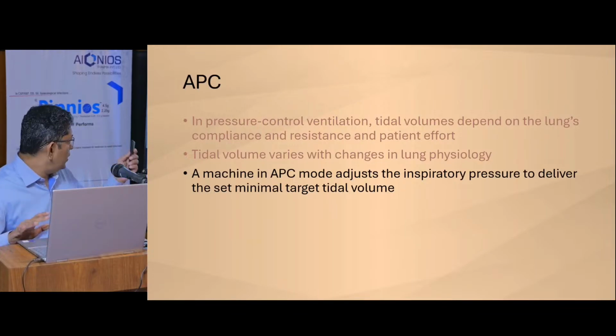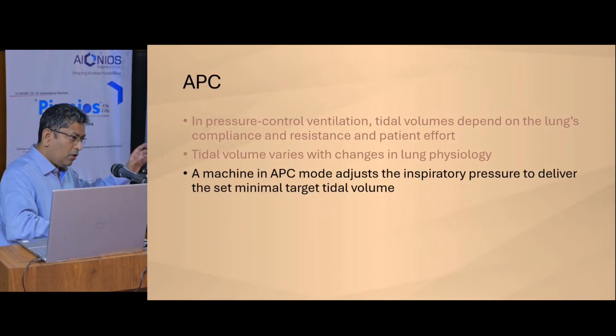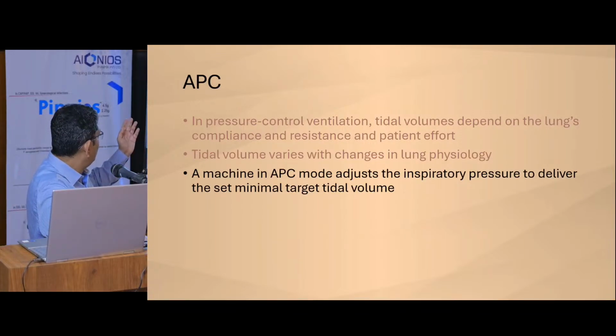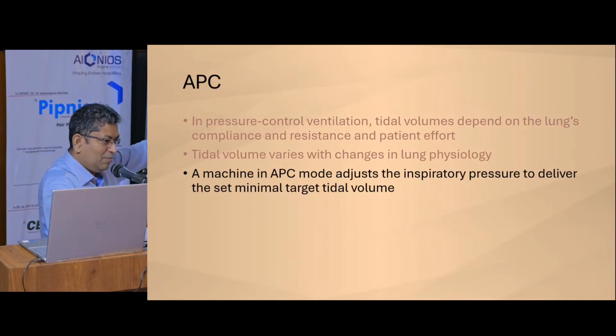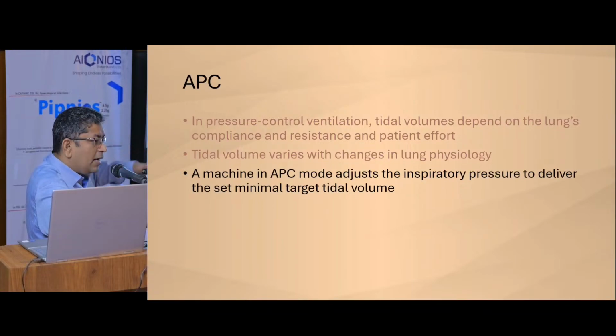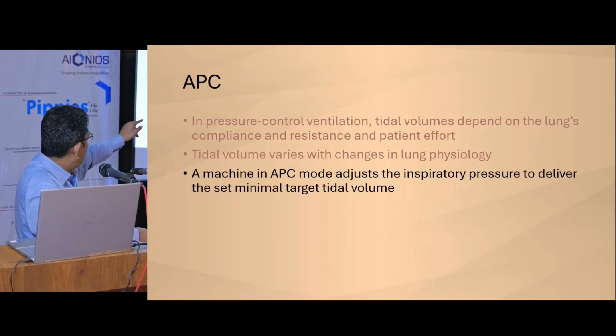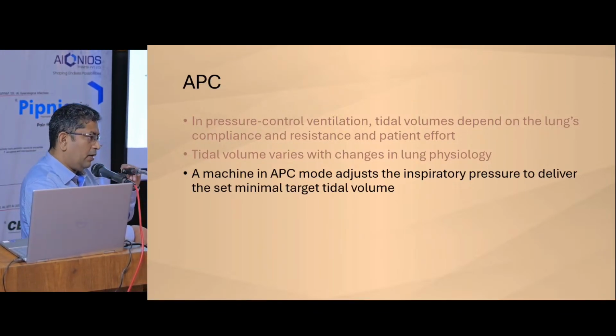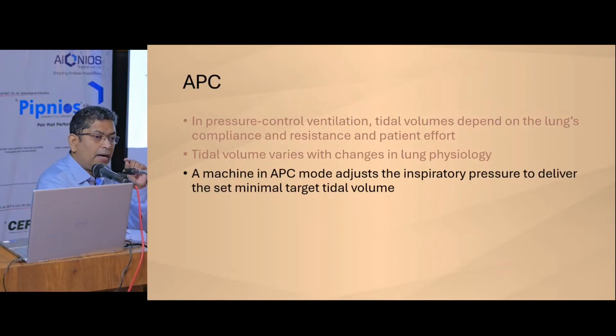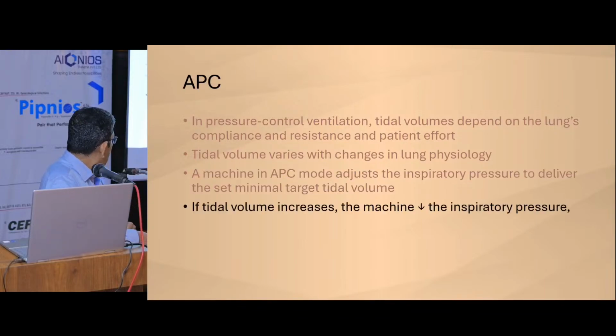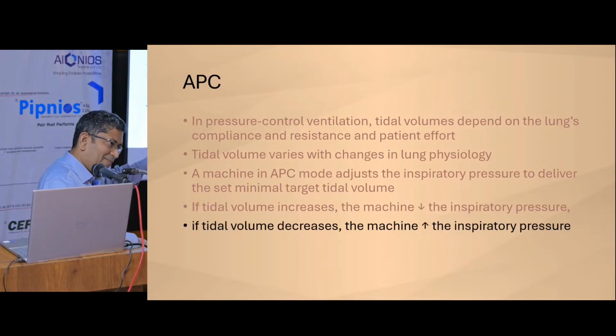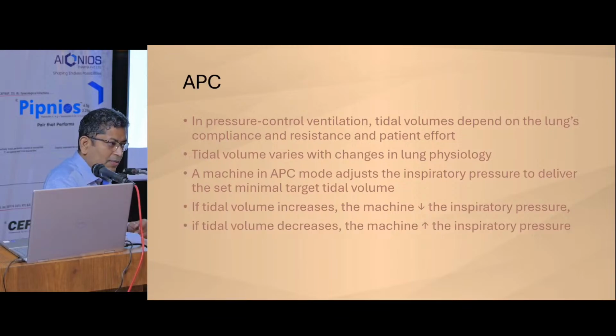So if you put a patient on this APC mode, or adaptive pressure control, or PRVC mode, as you are more familiar with, okay, the inspiratory pressure is adjusted to get a minimal tidal volume. So here also you're setting a tidal volume for the patient. The ventilator will, and then the other thing is, if the tidal volume increases, the machine decreases the inspiratory pressure, and vice versa. Okay, so that's what it does.